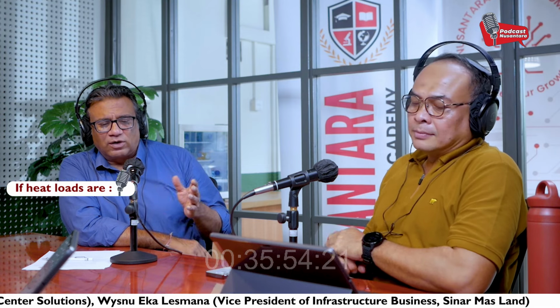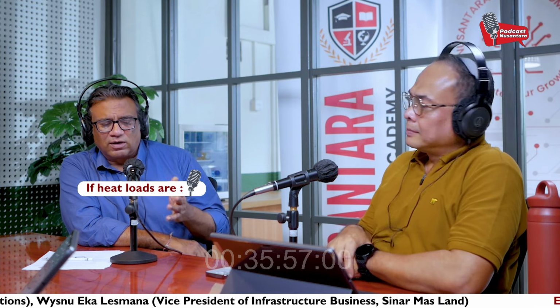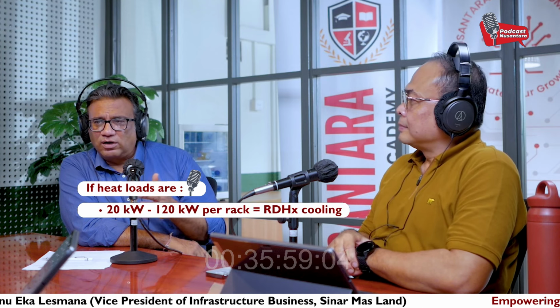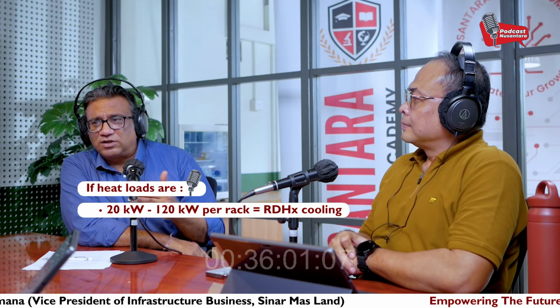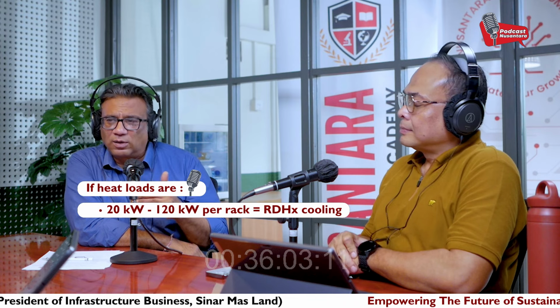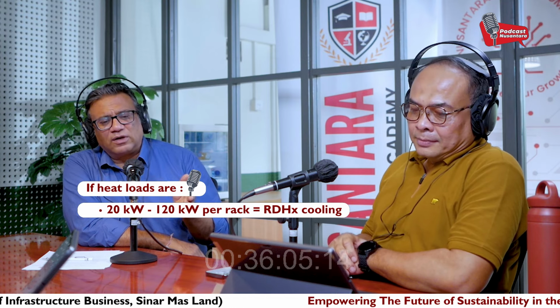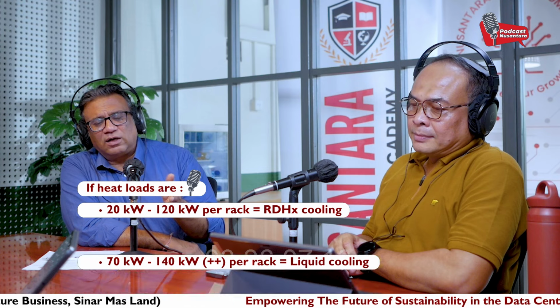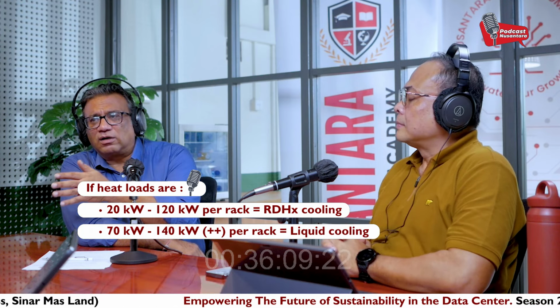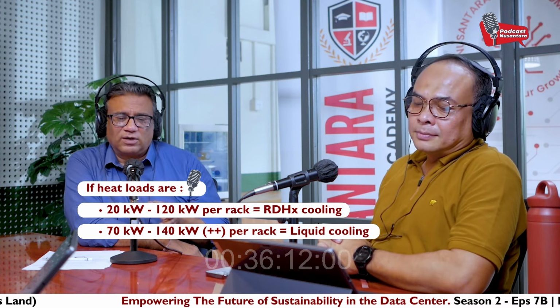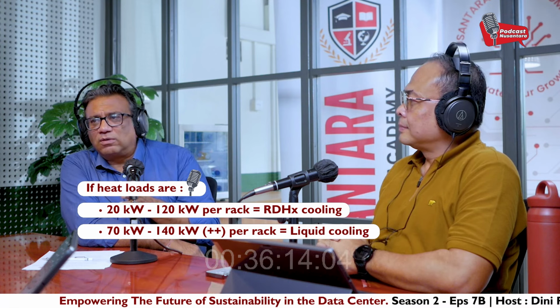As a thumb rule, we can say that if your heat loads are, let's say, 20 kilowatts per rack going to 100, 120 kilowatts per rack, a rear door heat exchanger becomes a very good viable option. When you start crossing heat loads of 70, 80 kilowatts and going to 100, 120, 140 plus, then you may want to consider liquid cooling.